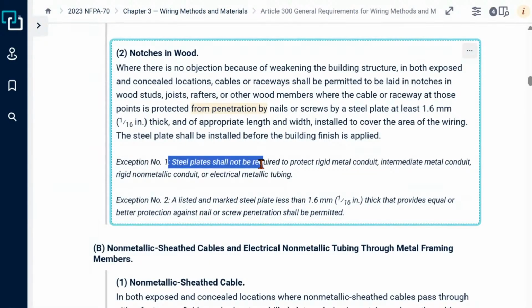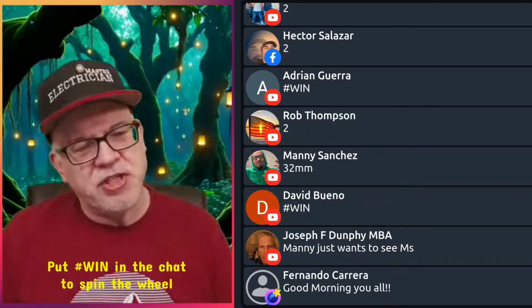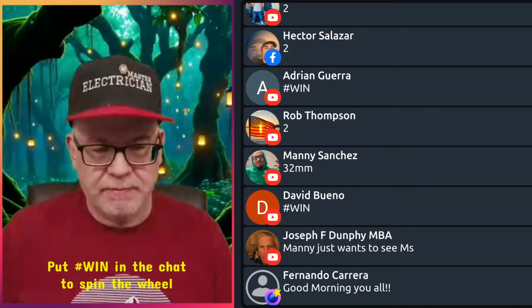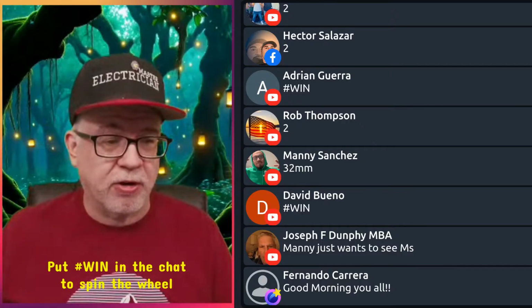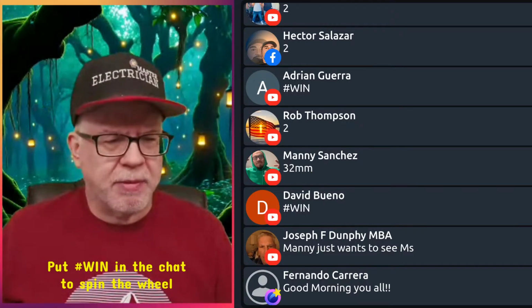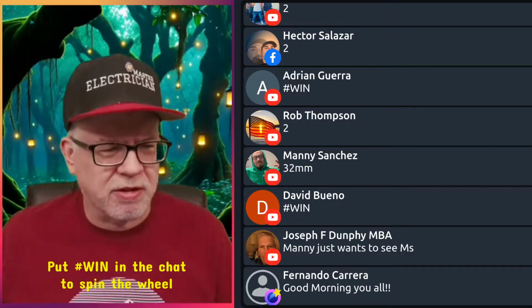Number one, steel plate shall not be required to protect rigid metal conduit, intermediate metal conduit, rigid non-metallic conduit. That's Schedule 80, believe it or not, folks, not required. Or, one cycle ago, they added EMT, electrical metallic tubing. So a lot of people say, wait a minute, Paul, you can't run NM cable inside of a conduit or tubing. Yes, you can, okay? Yes, you can. Whole different episode, but there's people out there that say you can never run non-metallic sheathed cable in a raceway. Oh, you most certainly can.